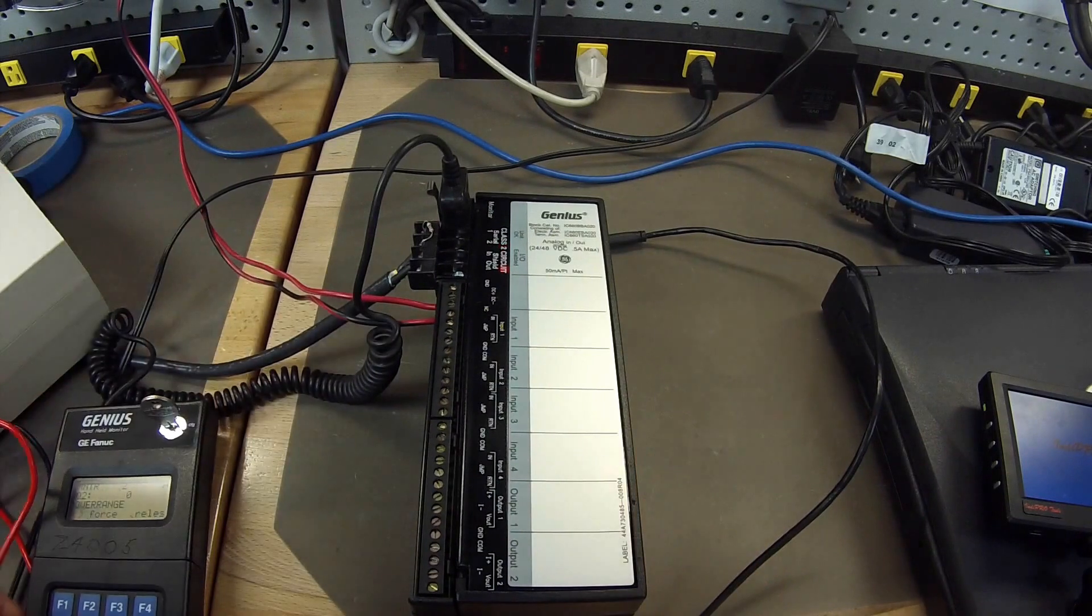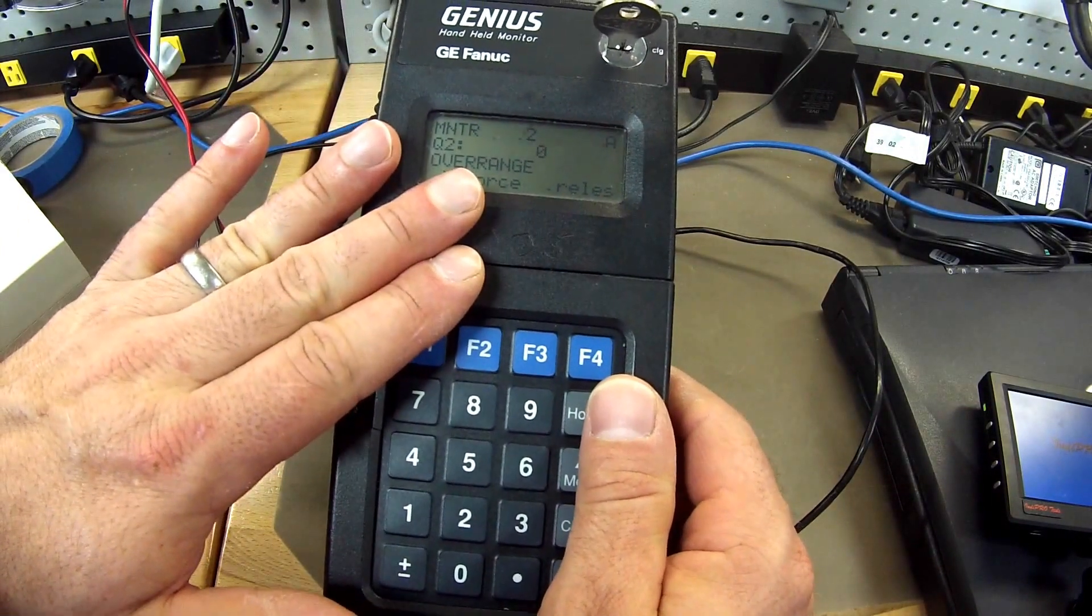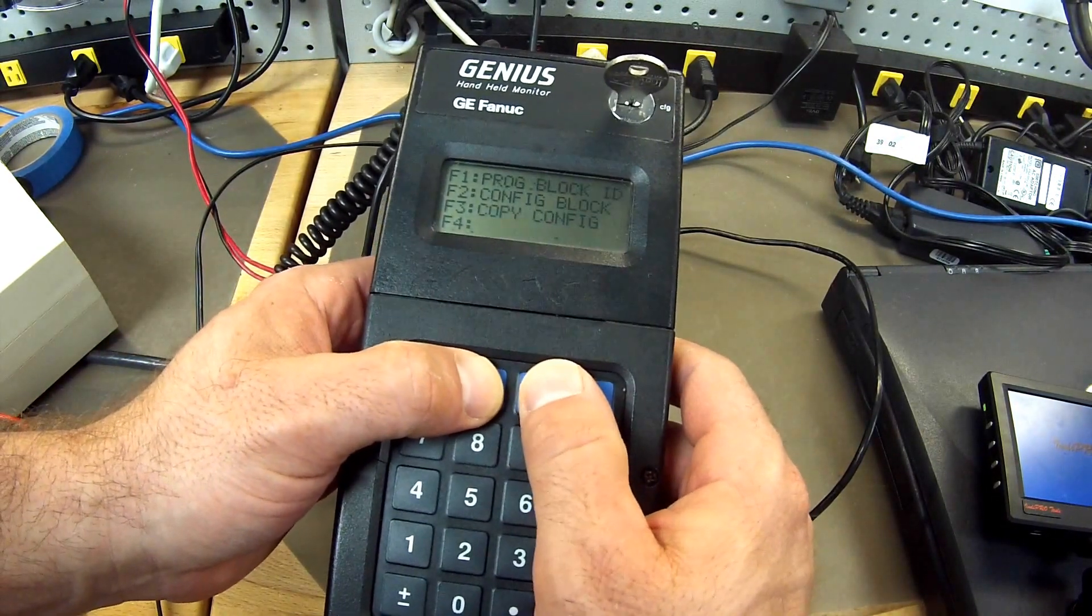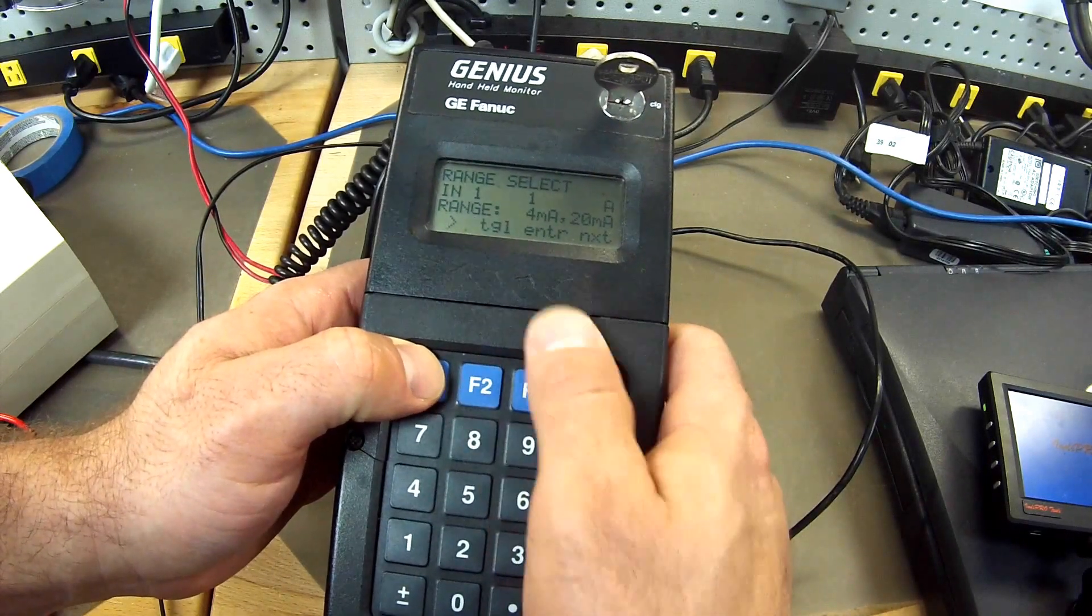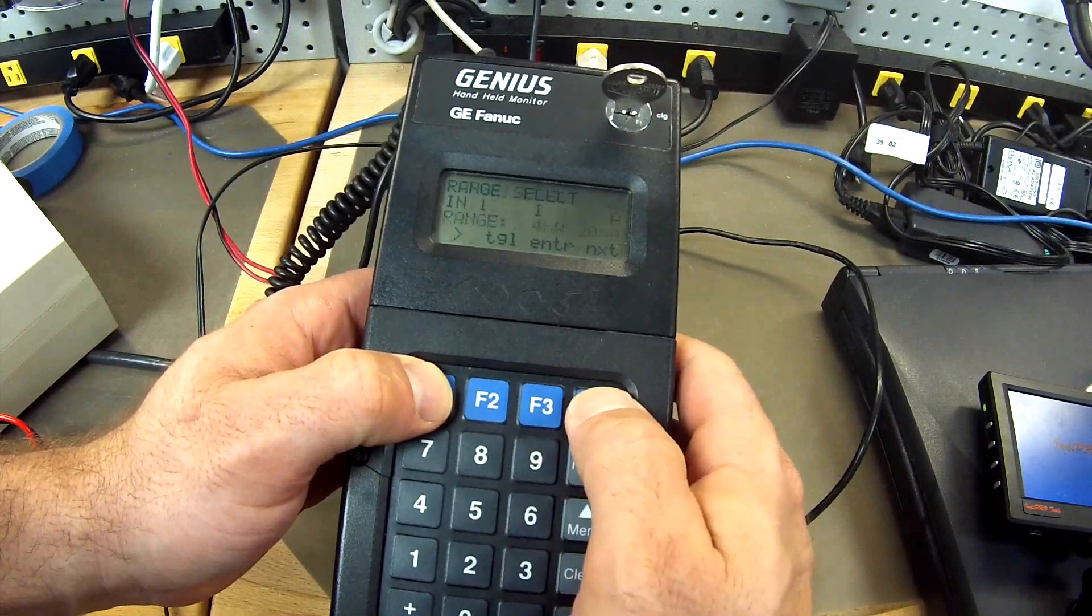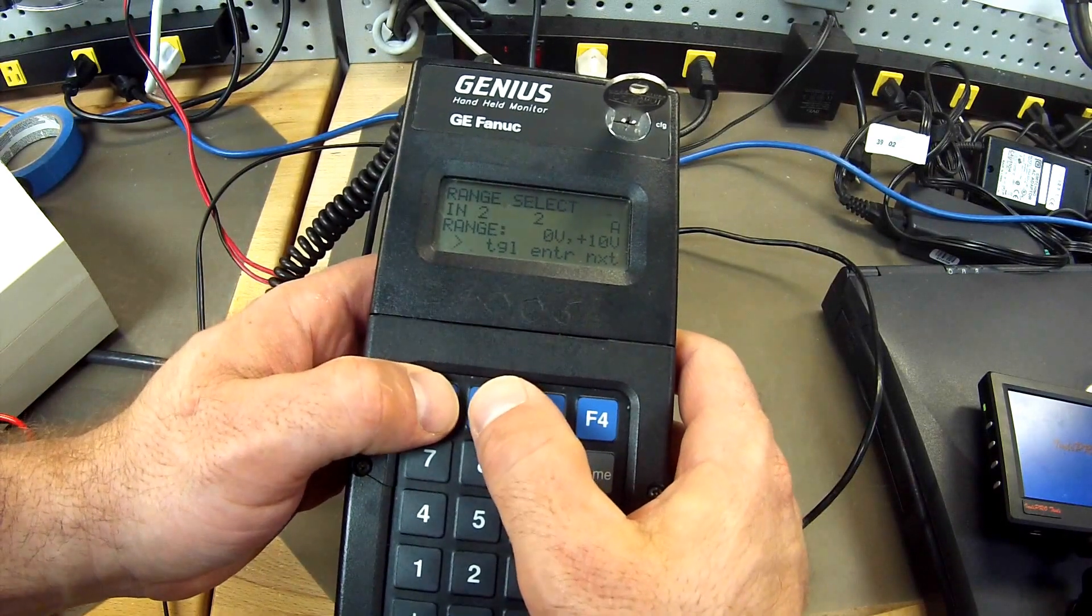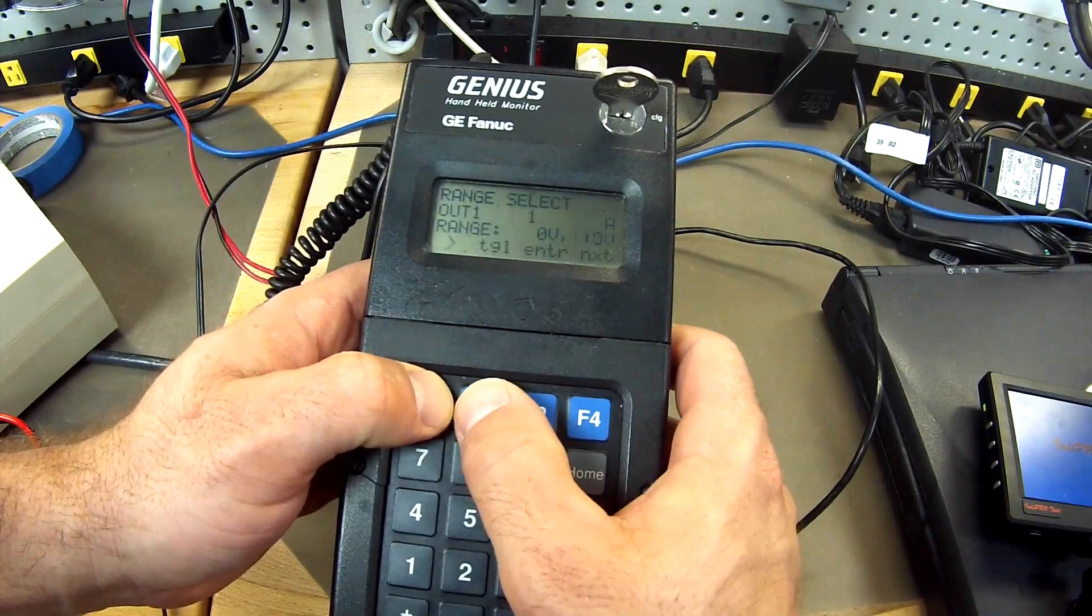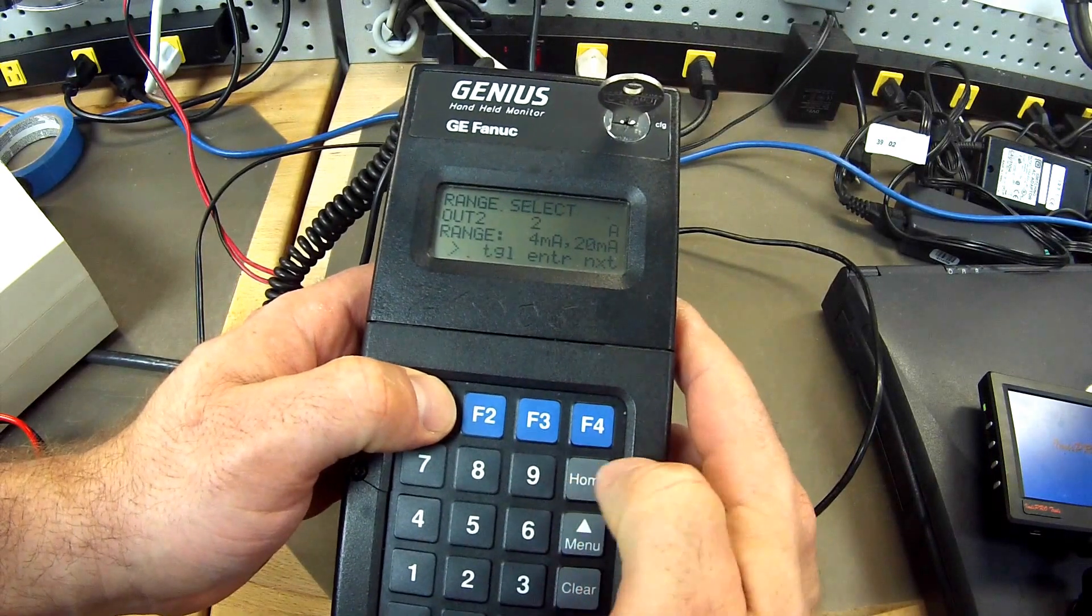Back to the handheld monitor. This is an IC660HHM501 handheld monitor. Go to configuration, F2 configure block. Here is my range. I am going to toggle 1, 2, 4 to 20 milliamp and hit enter. I have to do that with all of the inputs and outputs. You can toggle using F1 throughout all the channels. So these have all been entered. Now I am going to go back to home.